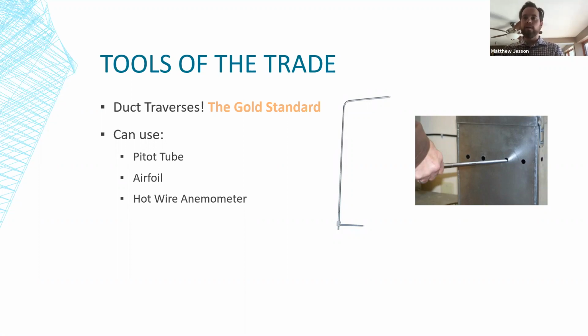The pitot tube is the classical tool for this. It was invented in the 18th century, and it has been changed very little over the decades and centuries. It's a very accurate instrument. It operates on extremely straightforward principles of physics, and it can be used with just a simple manometer. There are other instruments that you can use for duct traverses. The airfoil is one, and it's a lot like a pitot tube, but with a straight end instead of the 90 degree. And it works very well and very similar, but it requires an algorithm that's developed by, and it's sort of proprietary by the manufacturers of these instruments. You can't just use a simple oil-filled manometer to determine your differential pressure.